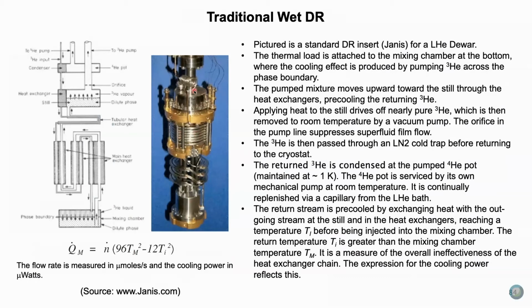dilution refrigerator. This is a picture of a traditional wet refrigerator. The mixing chamber is down here. There's a series of heat exchangers. There's a helium-4 pot up here, which is used to condense the returning helium-3 stream. Thermal load is attached to the mixing chamber at the bottom, down here. The pump mixture moves upward through what's called the still. Right here, this is the condenser right here. This is the still. And it's pumped on by a helium-3 pump at room temperature. And then is returned back by this stream, which is why you need all these heat exchangers.